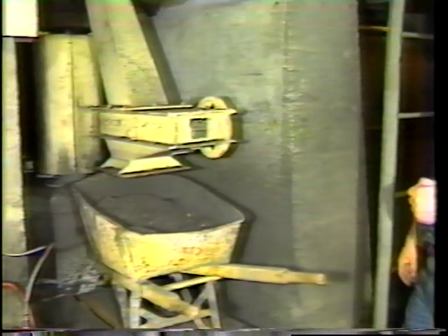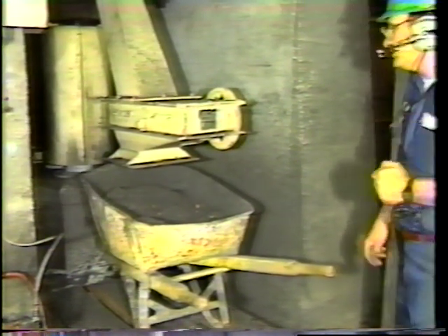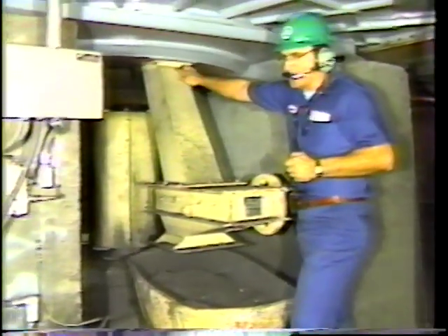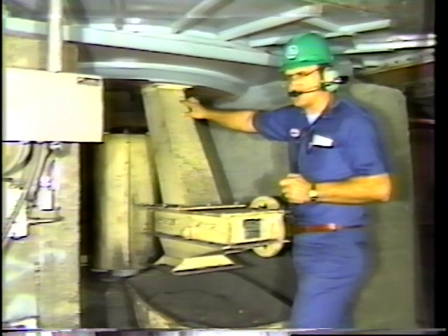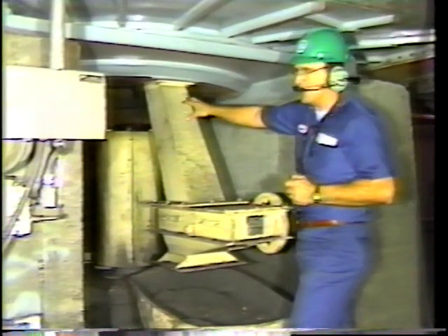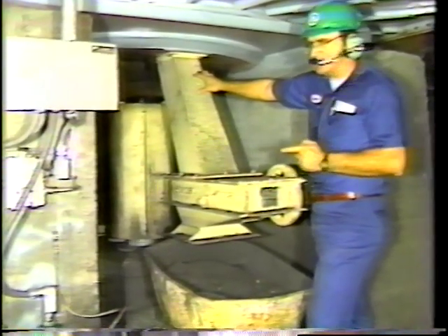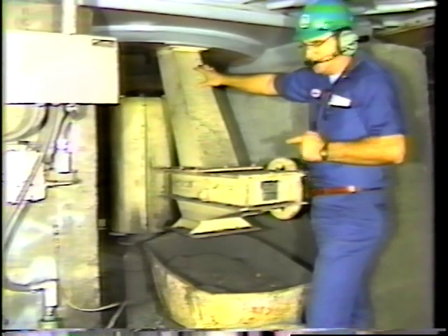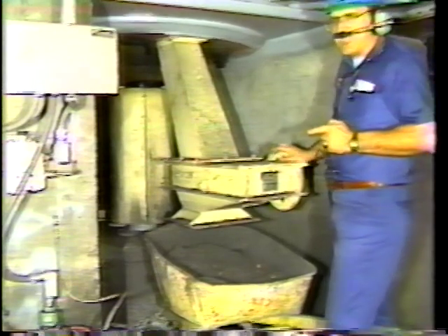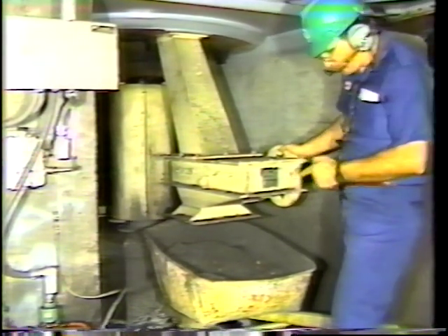Of the dry skid package for pulverizer number 3, boiler number 2. Up here, we have the discharge spout, which comes out at the bottom of the pulverizer for discharging tramp metal, pyrites, things of this sort that collect in the bottom of the pulverizer. We can open this while this mill is in operation and drain off a portion of the material into a wheelbarrow. It comes down this chute through this continuous slide gate and will discharge into the wheelbarrow we see here.